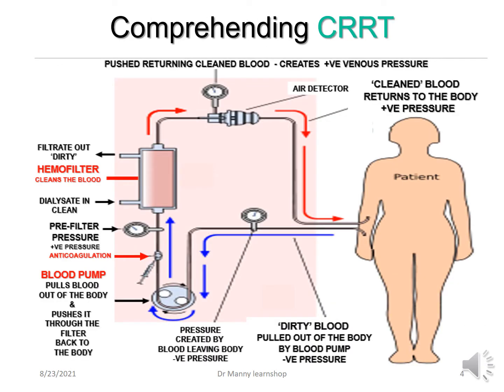To comprehend what continuous renal replacement therapy is: you've got a patient with access in the right arm, so blood is taken out — the dirty blood is pulled out of the body by the blood pump via negative pressure. The blood pump pulls the blood out and pushes it through the filter, then returns it back to the body. There can be anticoagulation, as you'll see in other Learn Shops, but it doesn't have to — it depends on the physician order and whether there's a contraindication or requirement for anticoagulation.